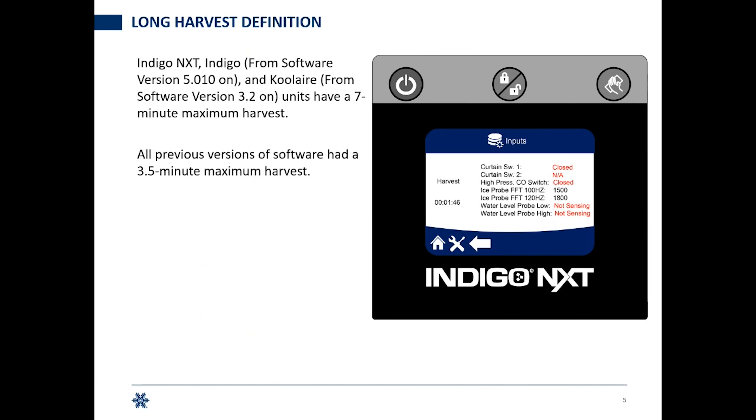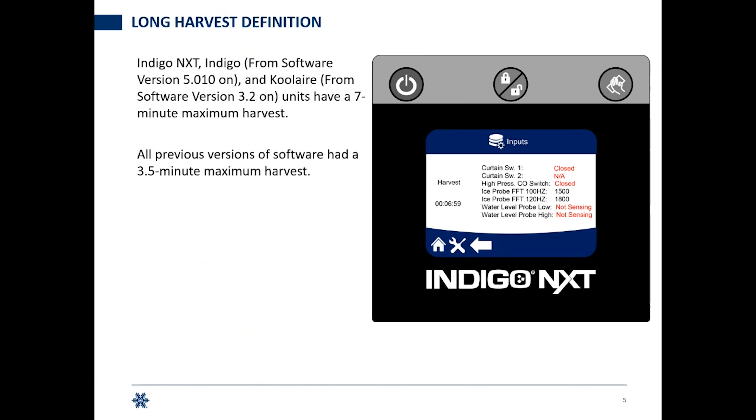Indigo Next and the previous Indigo series with version 5.010 software and on, and Koolaire units with software version 3.2 and on, have a maximum seven-minute harvest. All previous versions — Indigo 5.009 and prior, or Koolaire 3.1 and prior — had a three-and-a-half-minute maximum harvest. At six minutes and 59 seconds, you've got one second to drop that ice, and if you don't, you go into a thaw sequence. Do that three times in a row on Indigo Next and you'll go to an off state on long harvest.